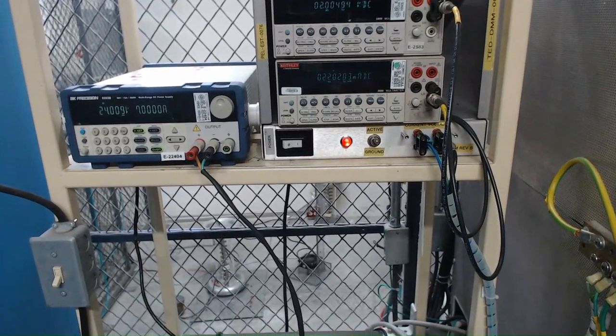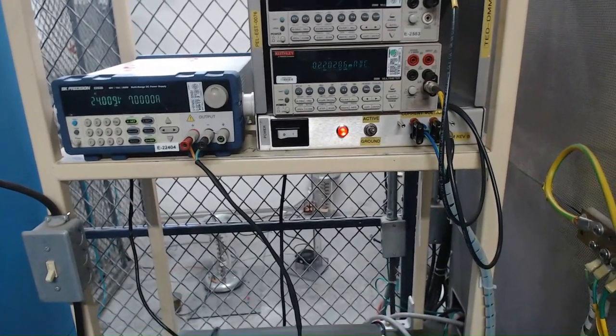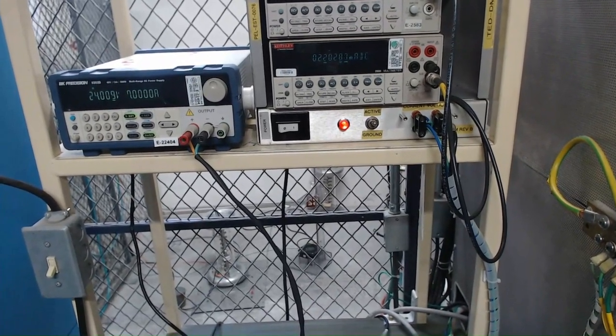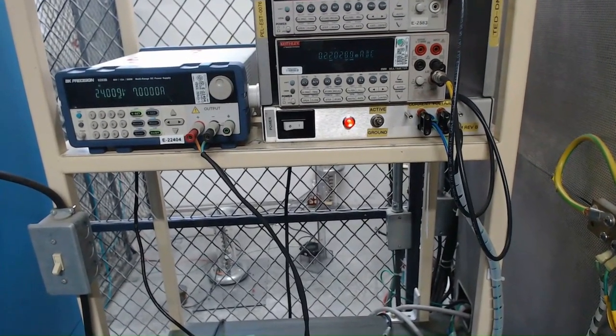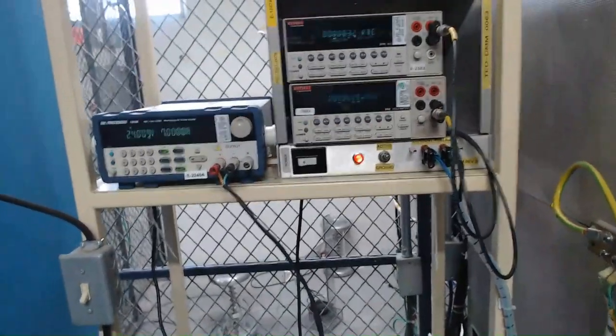It can be seen that even with the output set to 50 kV, the output voltage limited to a lower value to ensure current did not exceed 2.2 milliamperes. Value of the current limit is recorded into the datasheet.